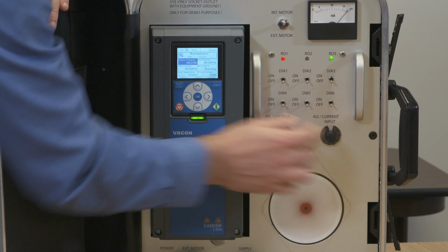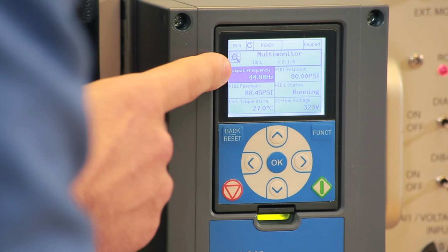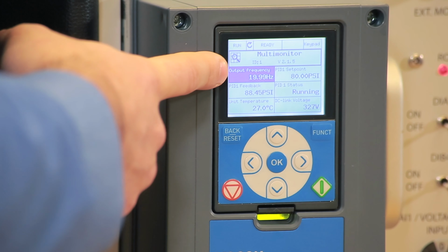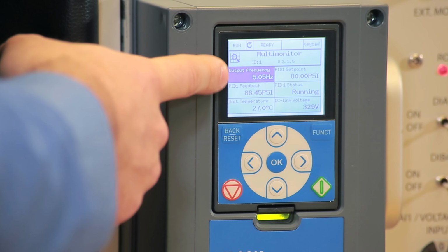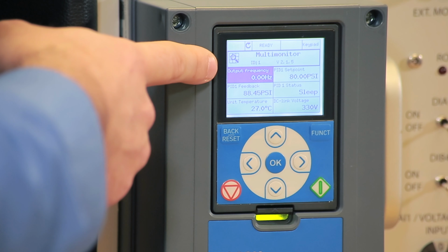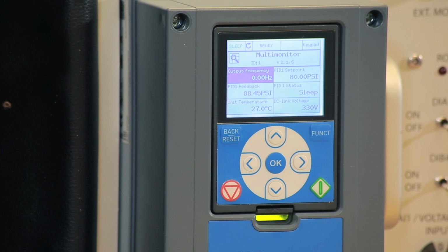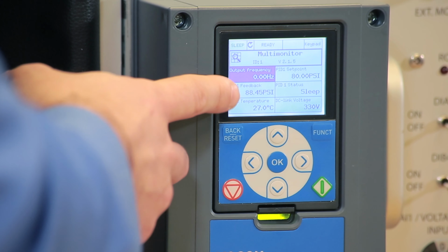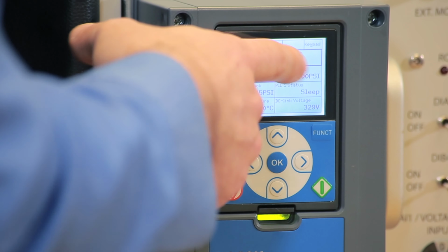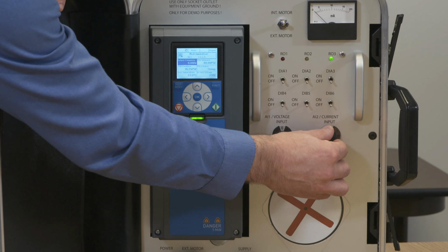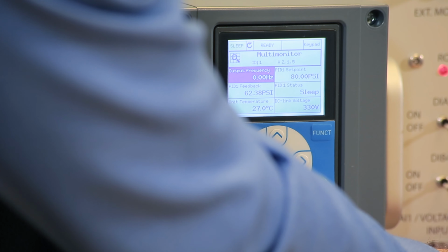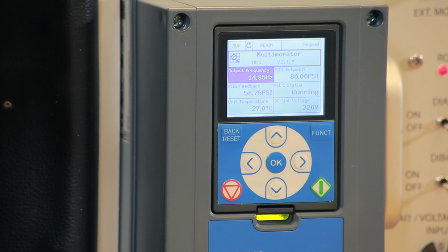And once the feedback goes above 80, the drive immediately slows down, and it runs the counter that we programmed, the 10 seconds below, I believe, 50 hertz, and now the drive says asleep. The drive is sleeping. So if this pressure feedback from 88 drops below 60, the drive should wake up, because our set point is currently 80. So let's decrease this value here to below 60, and the drive starts running.